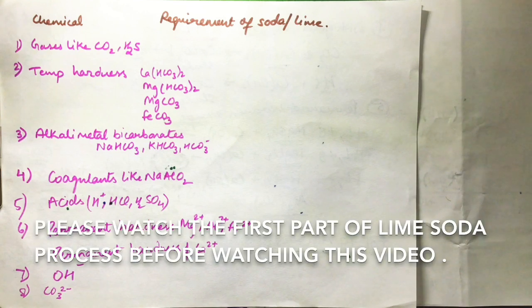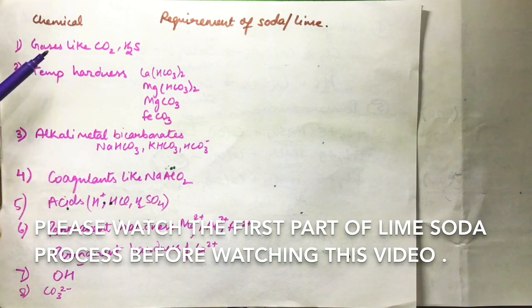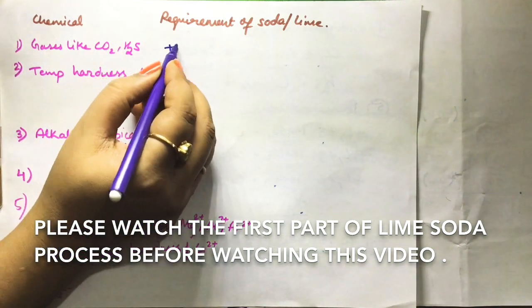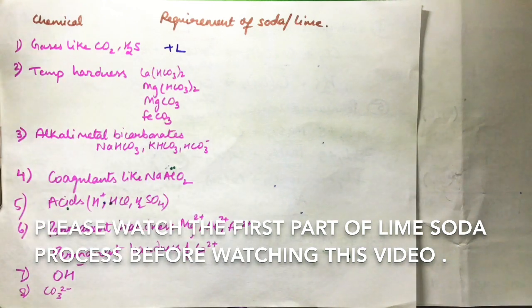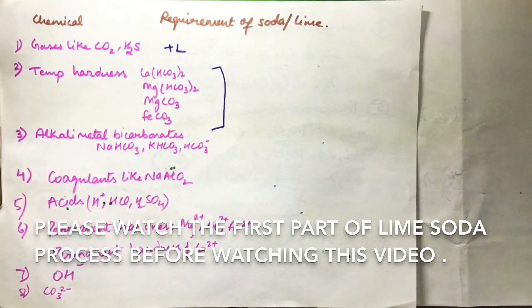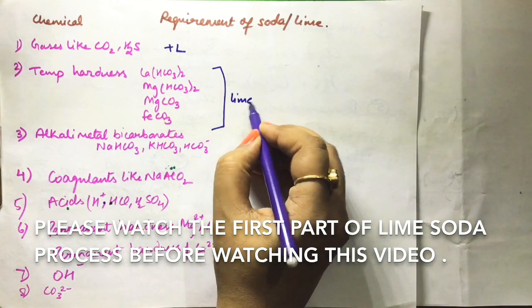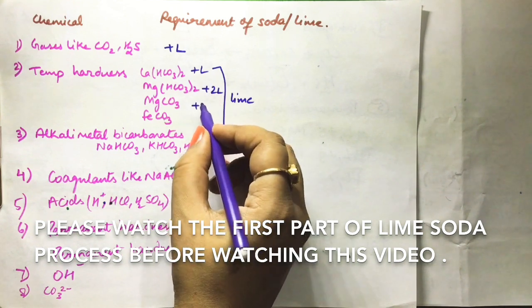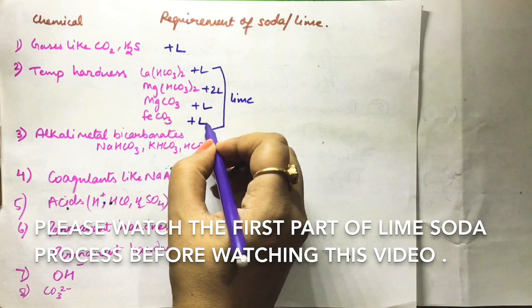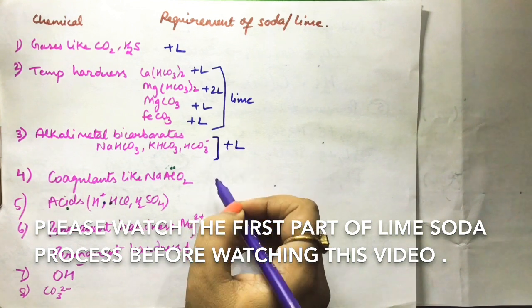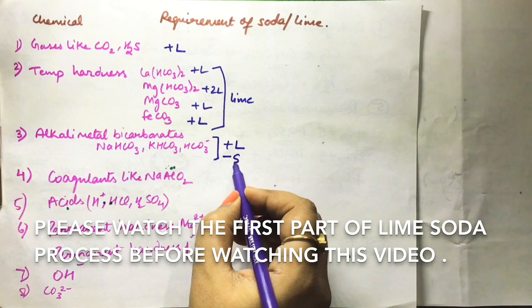On the basis of the reactions we have discussed, we can see every chemical we need to remove lime or soda. If we talk about gases like CO2, we know that we only need lime. Temporary hardness is always removed by lime. On the basis of the reaction, bicarbonates add in lime and subtract in soda.